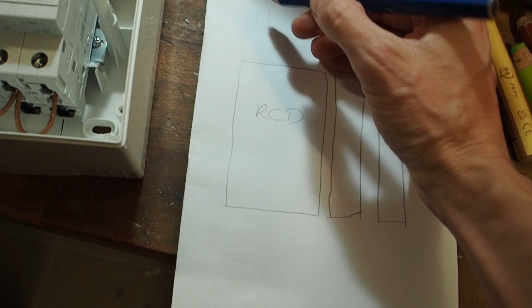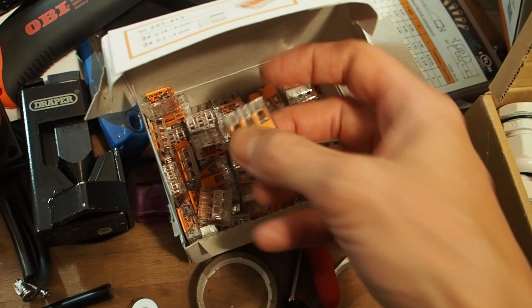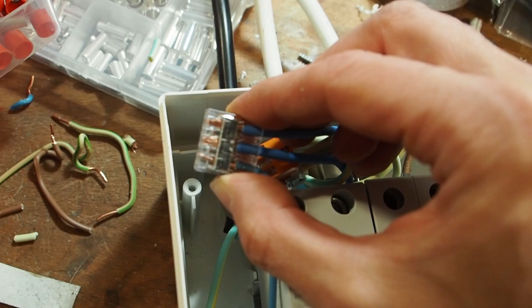Now we have three wires coming from the inverter, the blue one, and this one goes right into the RCD, and then it comes out here on the bottom. Then we go back up here, and here I've installed a Wago clamp. These are really great clamps by the company Wago, and you can use them with both single strand wire and multi-strand wire. They're really safe, effective, and fast. I really like those clamps.